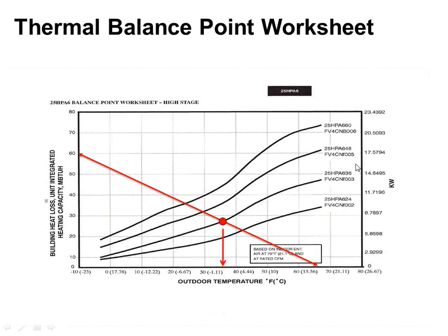Now, how do I pick between the 2, 3, 4, and 5 ton? Well, I need to kind of know the cooling load because I don't want to be grossly oversized here. And then I also have to think about how much ductwork airflow I can handle.